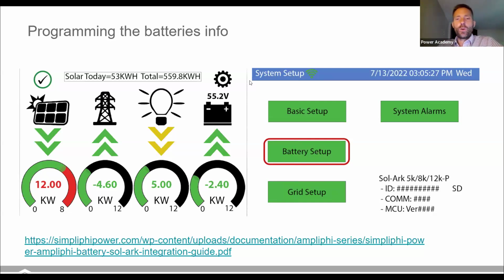So there are a number of things to point out in the setup of the Sol-Ark inverter. Basic setup will give you things like screen timeout, but there's also an advanced tab in the basic setup that allows you to program a limit on your generator input. So if you've got a small portable generator, maybe a 5K generator that you want to try to integrate and back up the house with, or maybe even an 8K, you can limit the overall generator power draw in the basic setup advanced tab.